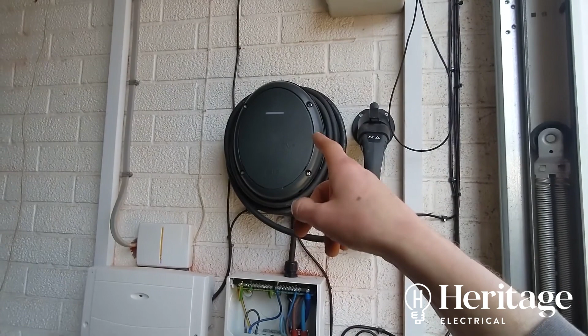In fact, it's coming off the main tail, so before we juice this up, disconnect the earth, get a ZE measurement, connect it back up, get the fault current measurement, line to neutral and line to earth. Do our dead tests, do an RCD test, and then we're ready to juice this up and register it with the DNO, get it all set up, and do a little handover for the customer.